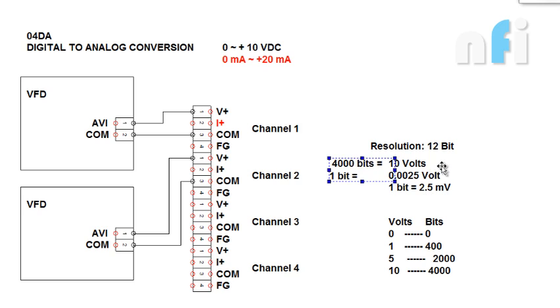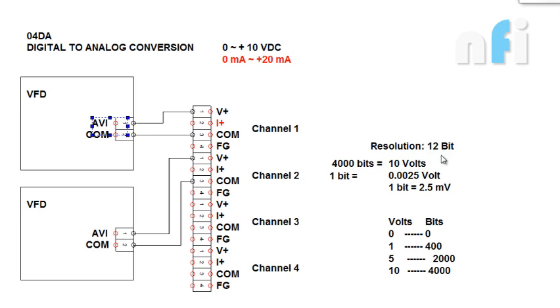If I give 4000 bits, it will give you 10V which is given to my drive. Or you can use this 0 to 10V on some other device like servo valves which operate at 0 to 10V, or any analog device, or servo motor if you are driving that in velocity mode.